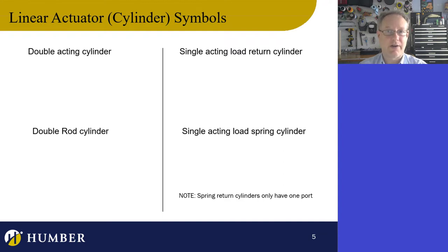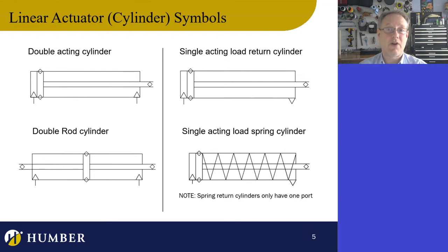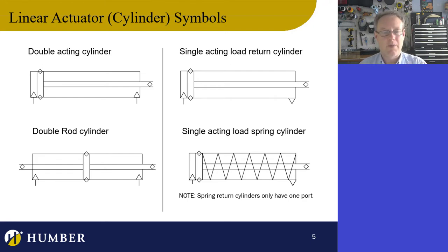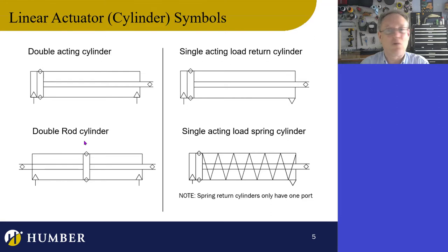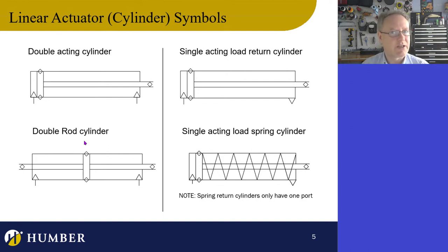Now let's look at the four different types of linear actuators we'll focus on in this course. First is the double-acting cylinder — the standard actuator we'll use in labs. If I put air in one way it retracts, the other way it extends. I can control both the extension and retraction force, and even the speed. Second is the double-rod cylinder — same application but with two rods. It's a rarer design but useful for specific applications where you need precise force control in both directions.